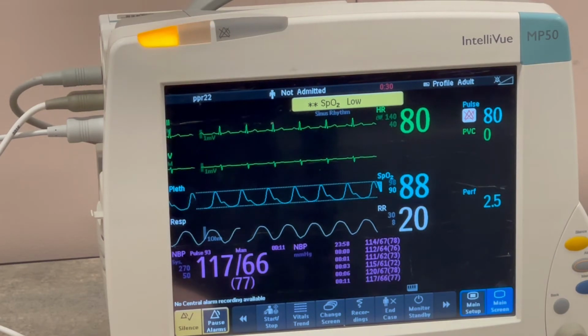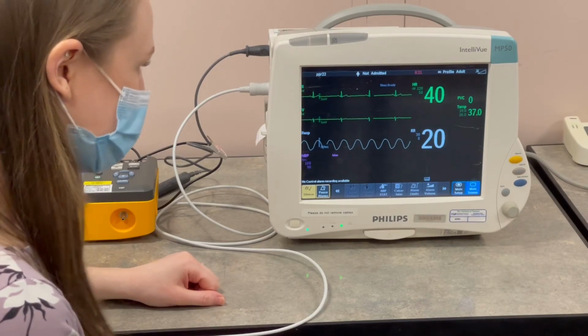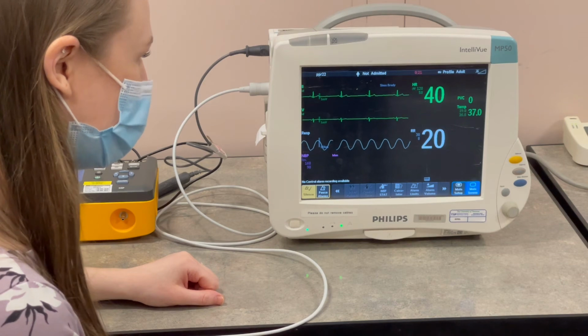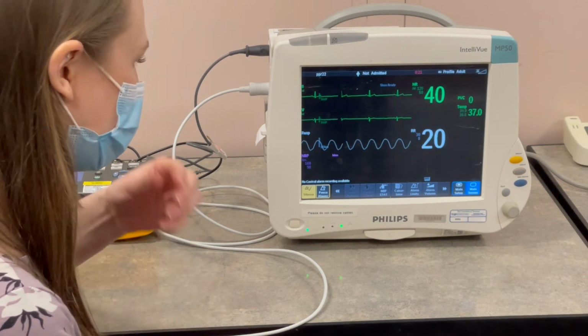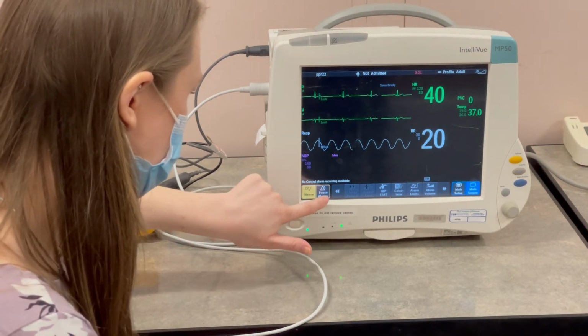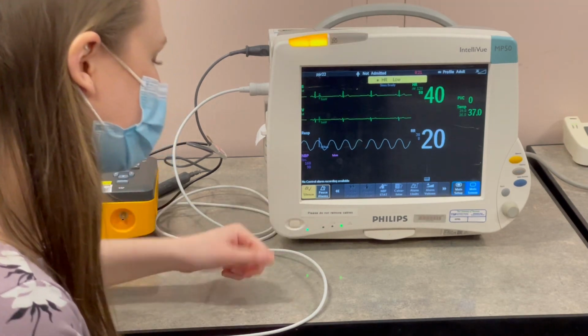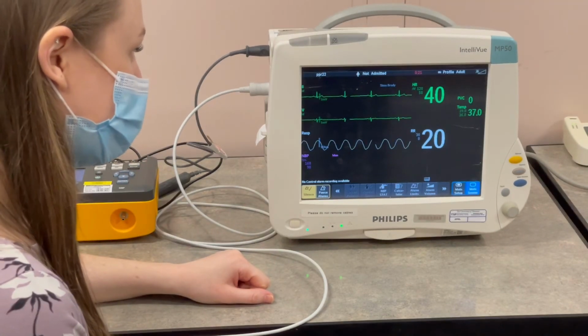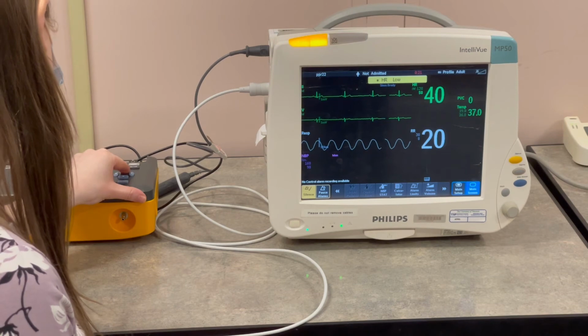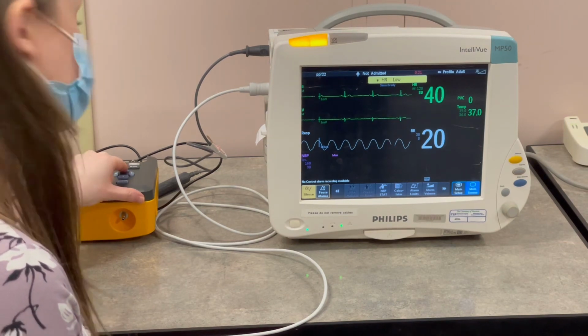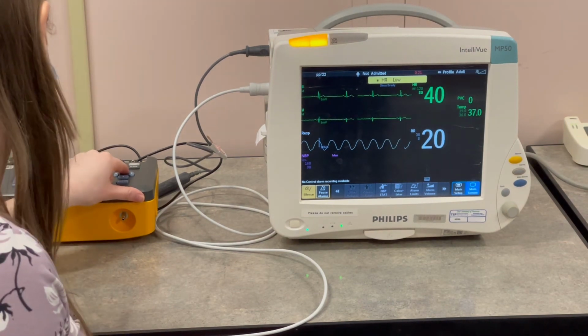mixture. For all alarms, the audible level should be adjustable and be loud enough for the user to hear in the patient environment where it will be placed. Visual alarms should be visible at distances where the user is typically located in the room. These items should be verified when the device is installed in the healthcare facility.